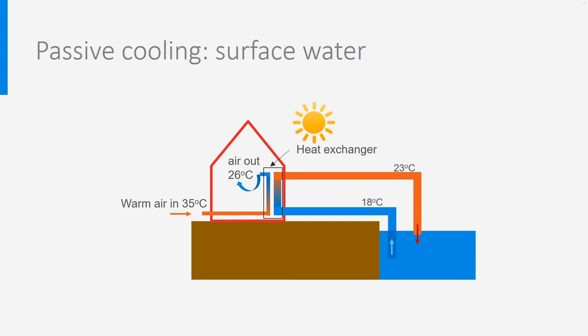This system is not completely free of electricity, as a pump is needed to pump the water through the heat exchanger and a fan is needed to circulate the air. By the way, this system may also be connected to a water system for floor or ceiling cooling instead of being connected to air. By using the simple equation, Q is mass flow rate times specific heat of water times delta T, it is relatively easy to make estimates of the needed water flow rate and the available power.